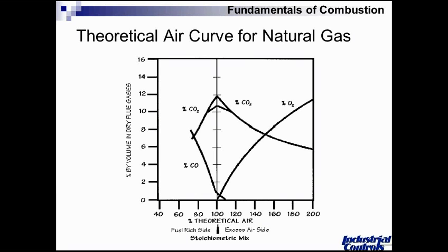You'll notice at the bottom we have a y-axis value of zero and the vertical intersection at 100% theoretical air. You would think that in reality your CO would drop to zero at the point when your free oxygen drops to zero. That would in theory be true, but when you look at any burner application it's very difficult to maintain enough mechanical reaction to cause the fuel and air to mix intimately enough so that absolutely everything is oxidized and there's no leftovers. Kind of like when you plan a party at your house, you always have more food than guests. You always want to have some free oxygen left over, some free food left over.